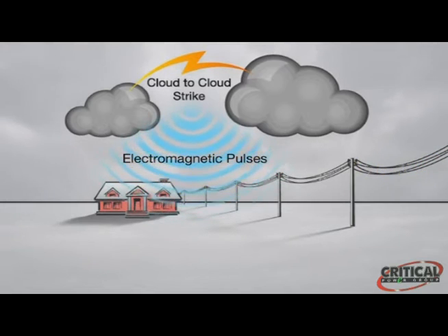Current from lightning can range from a few hundred amps to more than 500,000 amps. But 80% of transient surge events originate internally — caused by equipment motors starting up, lights going off and on, printers, switching motor loads, elevators, and any number of other events. They're usually not as robust as external events, but they're much more frequent.